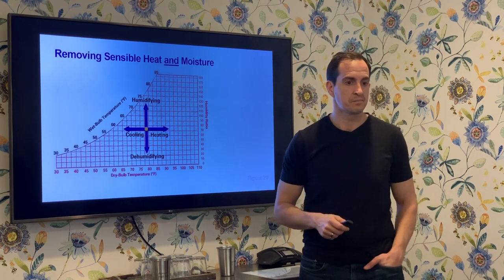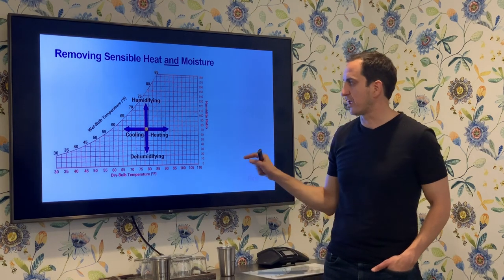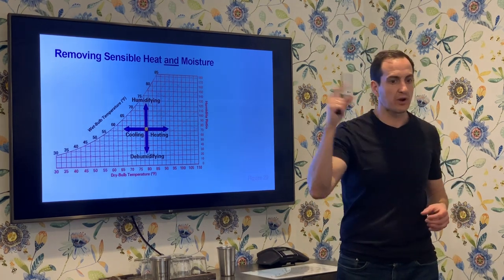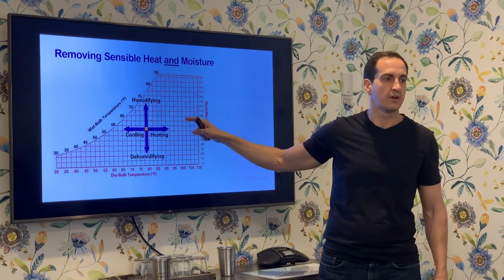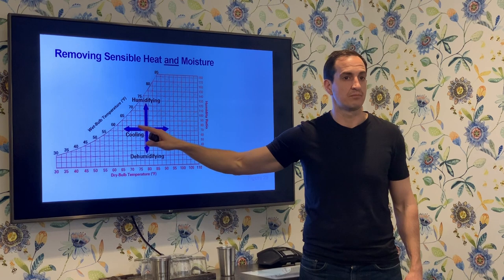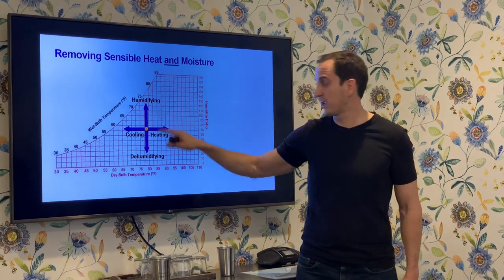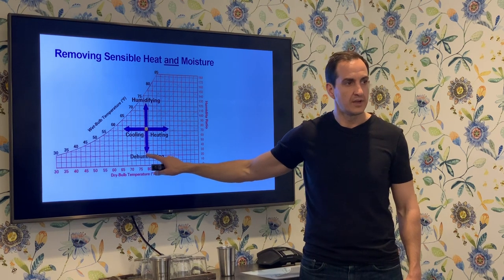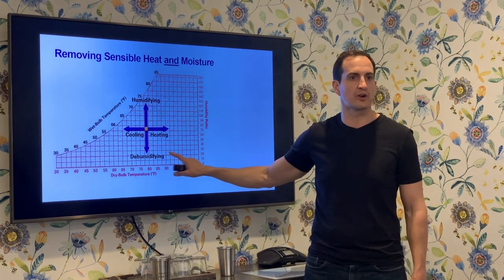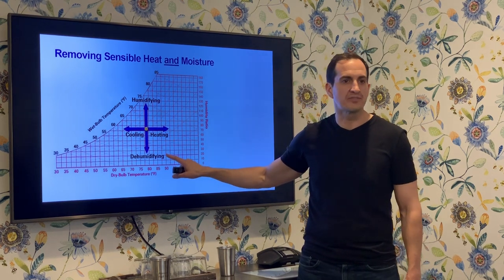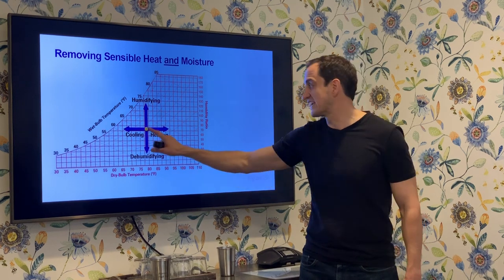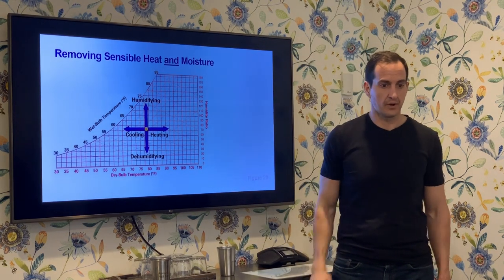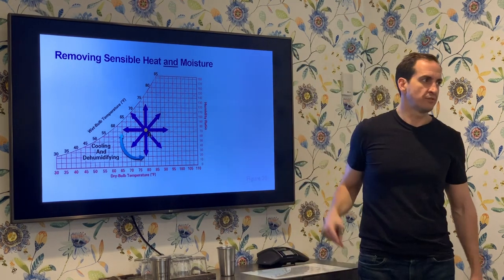The net effect matters: if I take a point on this chart and apply some processes to it, the arrows from where I begin to where I end are our cardinal directions as to what that process did. If I start here and end up higher, I humidified — no matter which path I took. If I start here and end up lower, I dehumidified. If I start here and end up to the upper right, like in so many grow room applications, I have heated and humidified the air.